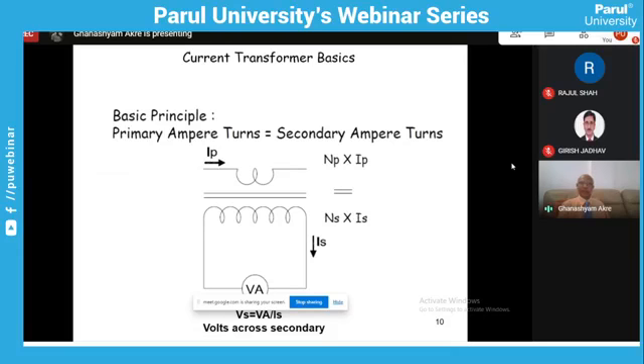Now, this is the case of the ideal transformer. Here, when you connect a meter or a protection relay, which has very low resistance and presents a VA burden, current will start flowing in the secondary. And the drop across the relay or meter will act as the voltage. This voltage is developed across the secondary. Current is constant at 1 ampere. So suppose there is a 5 ohm relay producing 5 ohms of impedance, then 5 ohms multiplied by secondary current, that is 1 ampere, the VA burden will be 5 VA, 5 volt ampere. So this is how it is calculated. If this is connected at a larger one, then accordingly the VA burden will increase.